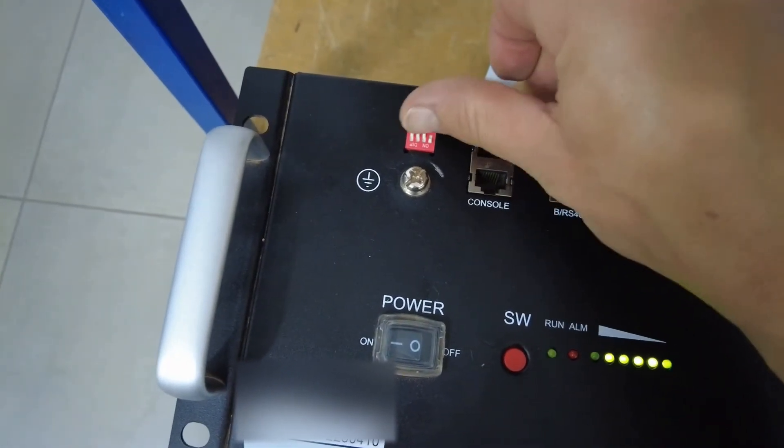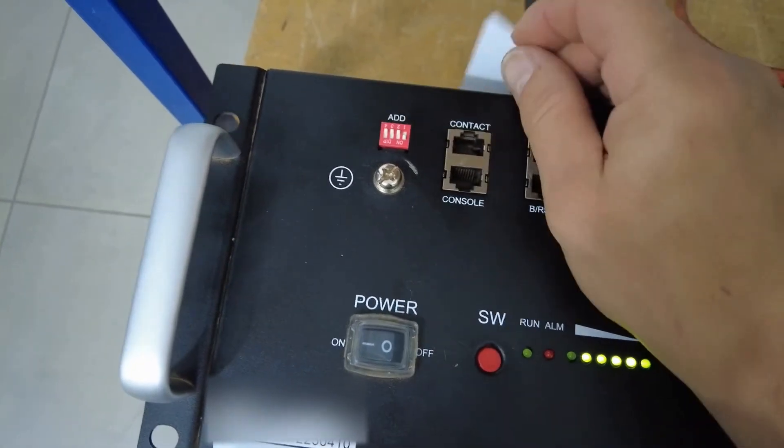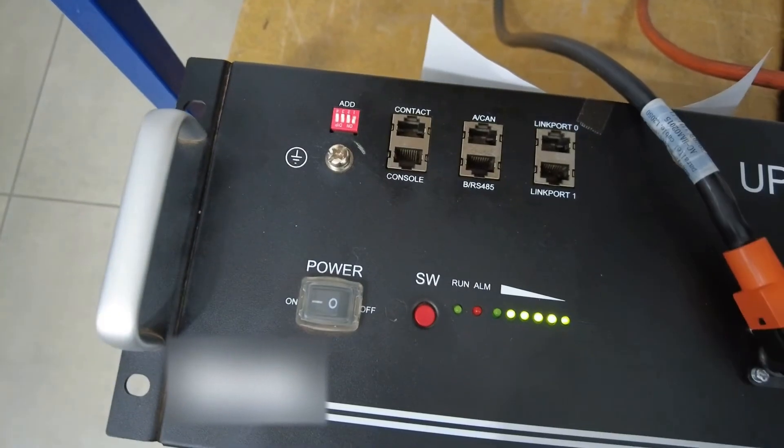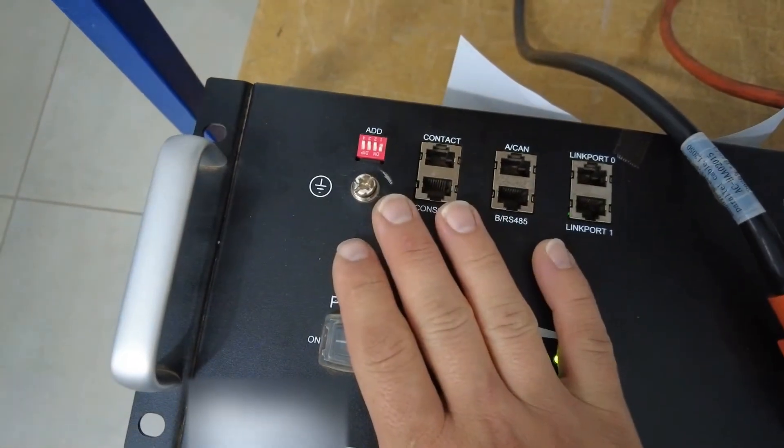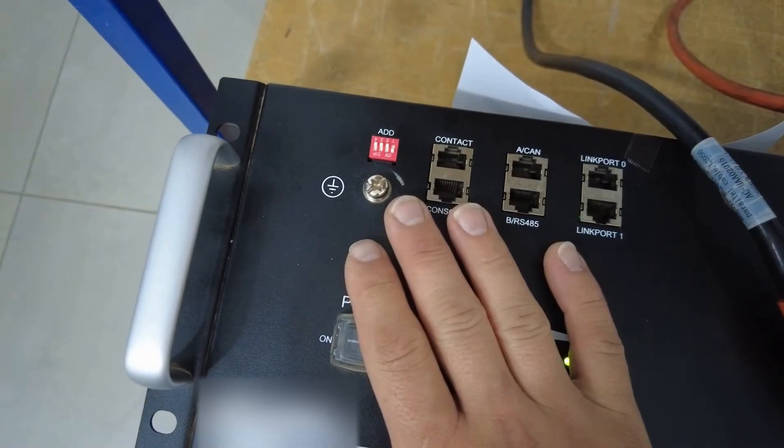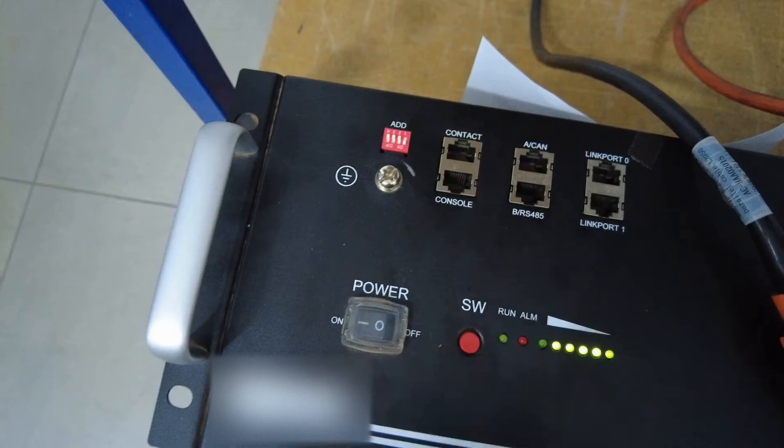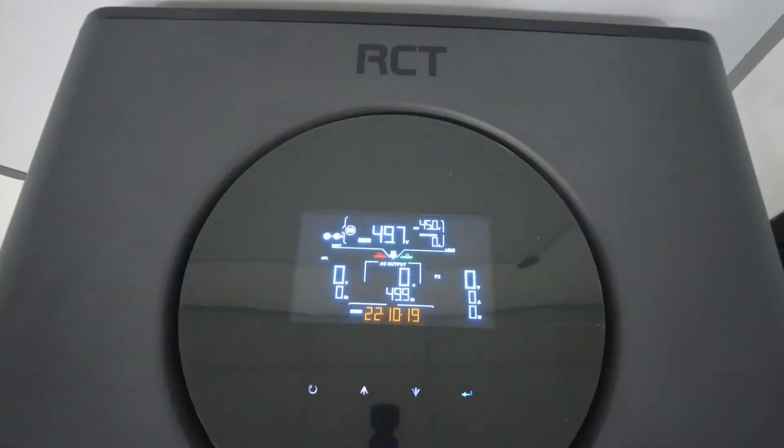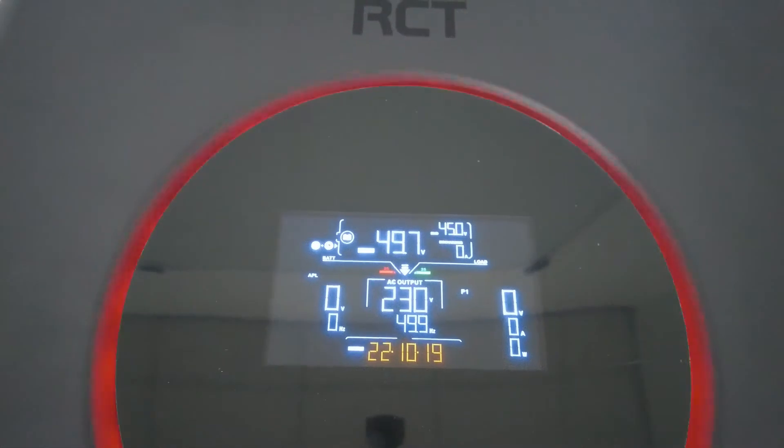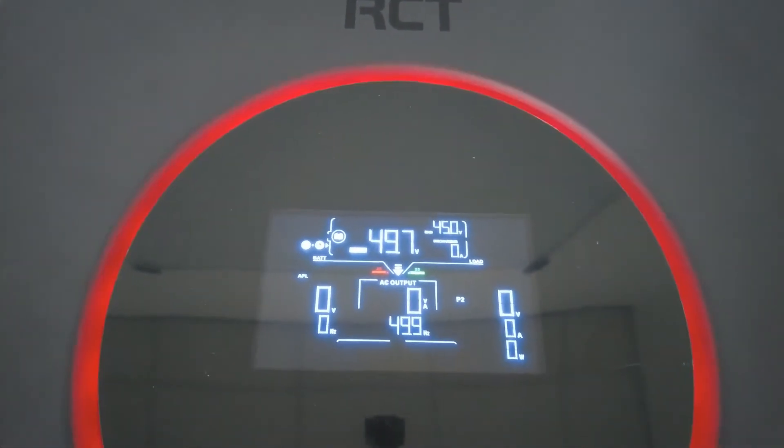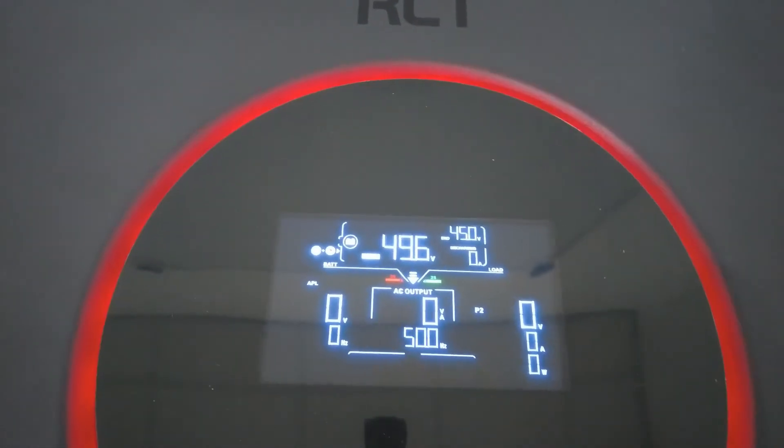The correct setting is DIP switch number one in the on position, and DIP number two, three, and four in the off position. Just be sure to set it right side up. Make the setting while the battery is off, otherwise the setting will not take effect. Currently it is displaying a 61 warning because I do not have the communications cable connected as yet. Because it's giving you a 61 warning, it is set to the lithium-ion setting already.